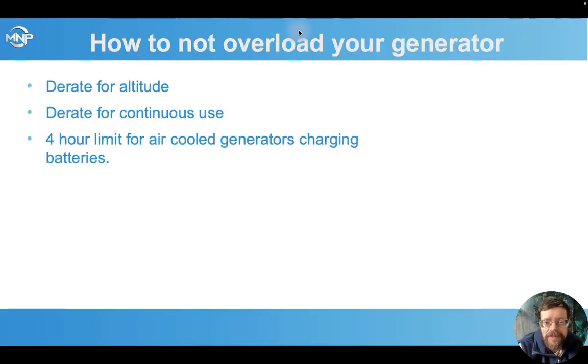We also want a derate for continuous use, because when we're charging batteries, we're drawing that full power for long periods of time. And most of them, even though they have a continuous rating, really aren't designed for that full max load for a long period unless they're a prime power generator. So when we're talking about standby generators, and especially air-cooled standby generators, most of those, we don't want to run them more than 4 hours at that maximum power, even accounting for these derates when we're charging batteries.